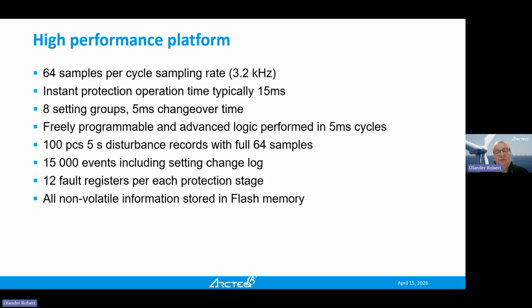Disturbance records, we can store 100, 5-second disturbance records with the full 64 samples. So actually this is probably more than anybody will ever need. Or if you get more than 100 failures in your network, it's quite much. 15,000 events will be stored in the memory, and for each protection stage there will be 12 fault registers, so it will register the fault currents and duration and the timing of the fault and so on. Of course, nothing special there, but I think we have quite many of those also.